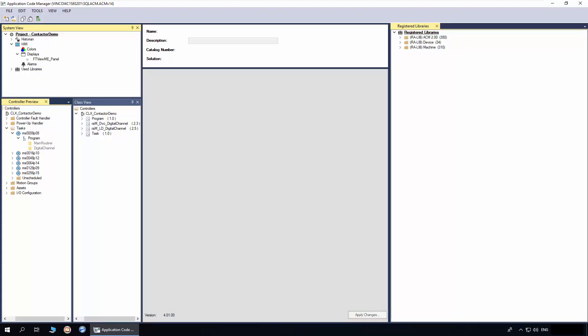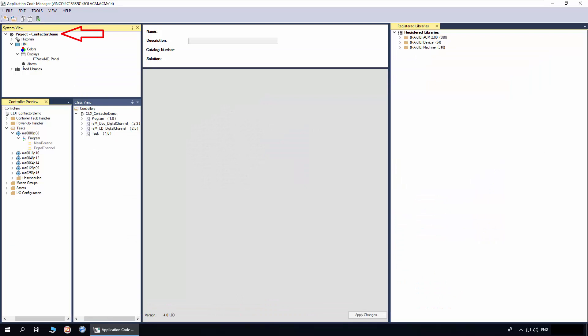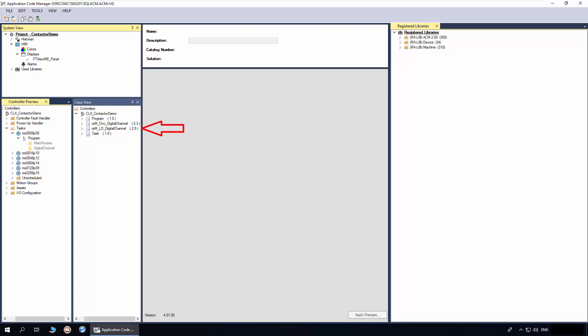In this section, I will demonstrate how to instantiate contactor and contactor feedback objects in Application Code Manager. The ACM already has the machine library registered. You need to download the libraries from the Rockwell Automation Product Compatibility and Download Center page. I have already created a project, added a controller and display, and added a program in which we will instantiate contactor implement objects. For the input and output connection, I have added digital channel objects.